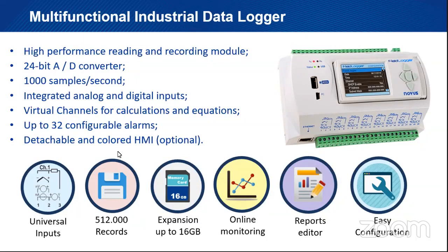It does have a report editor, so you can generate reports. Very easy configuration, and that's going to be proved today. I'll show you how the configurations are done. We have on the inputs a 24-bit AD converter. We reach up to 1,000 samples per second. So for very fast systems where you need a very quick sampling rate, the field logger is ideal.